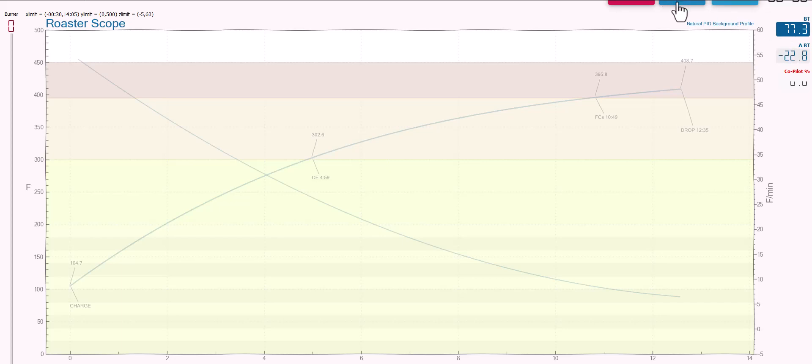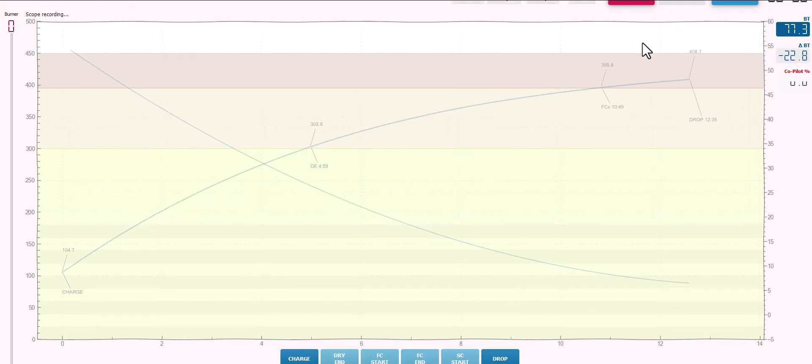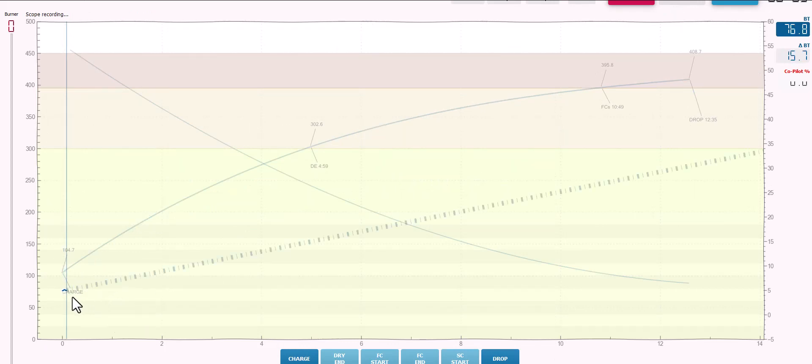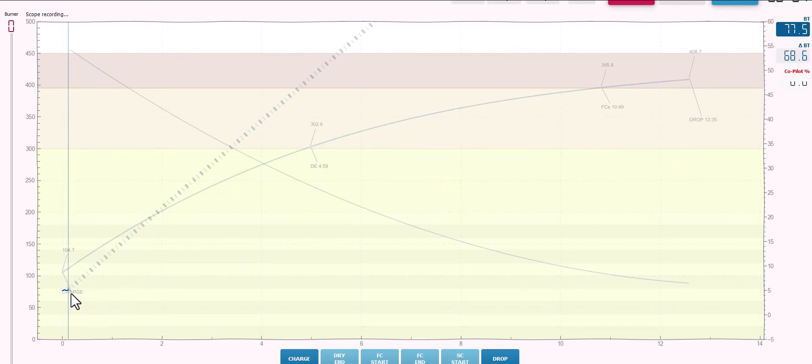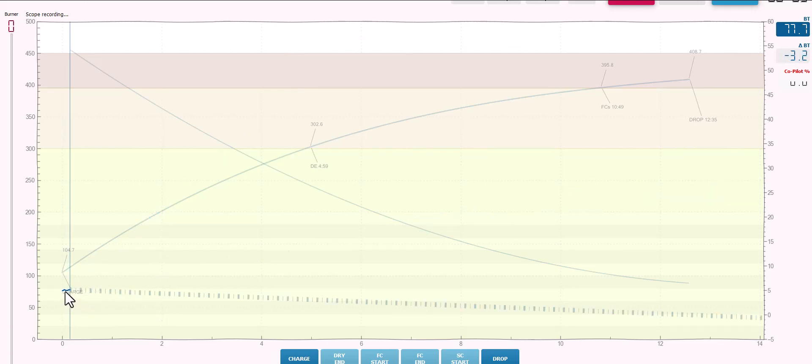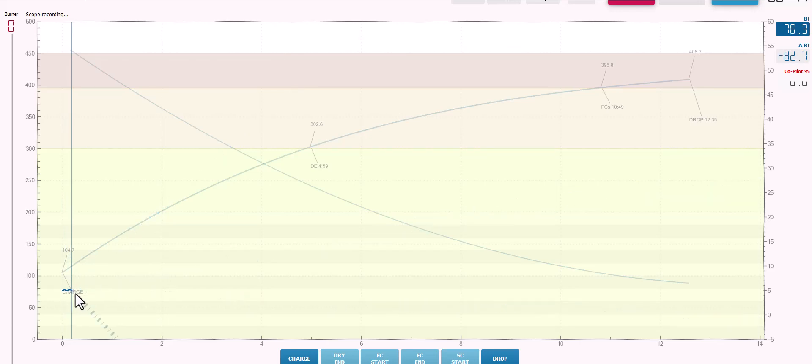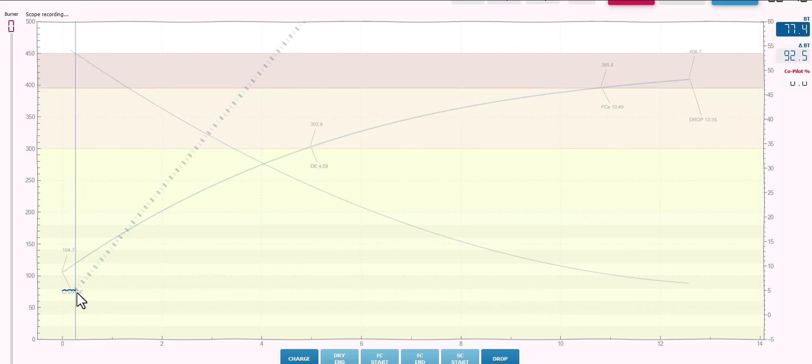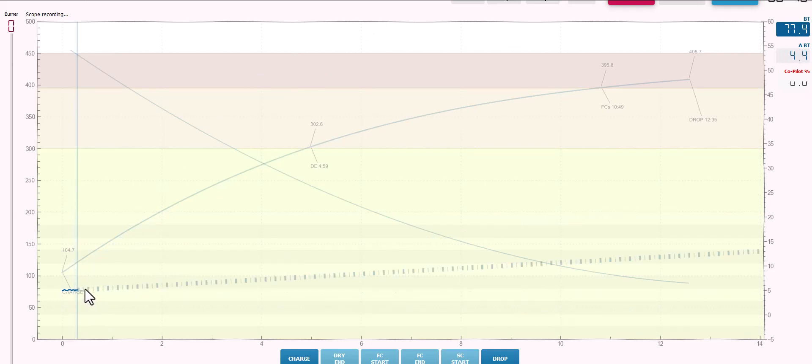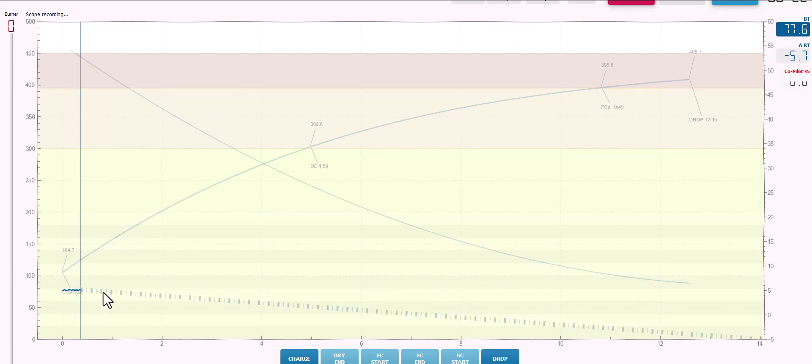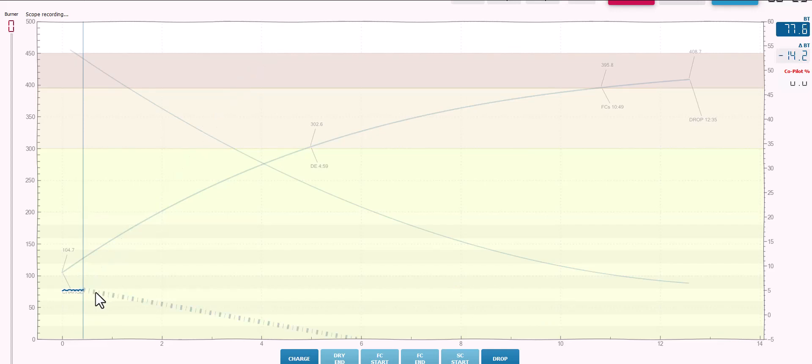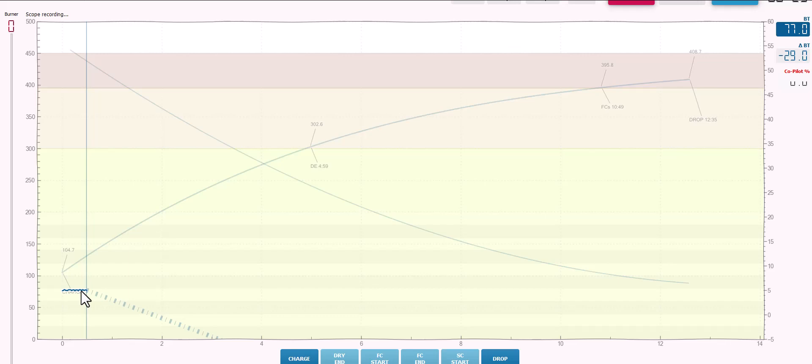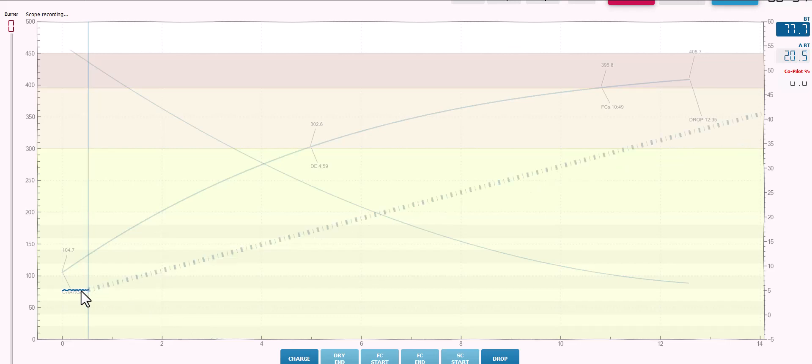If I clicked the start button, I'm not quite capturing the entire screen, but that blue button there is the start button. You can kind of see that I'm now graphing a temperature. And if we look at this line, it looks like it's fairly stable, and we might look at that and say yeah, this is a pretty decent thermocouple here. But it's really not. This is a terrible thermocouple, and especially if you're using PID to control your heat, this is an unusable temperature reading.